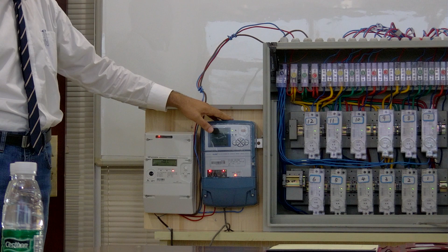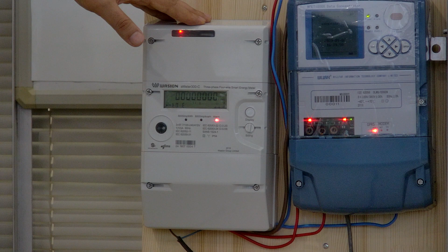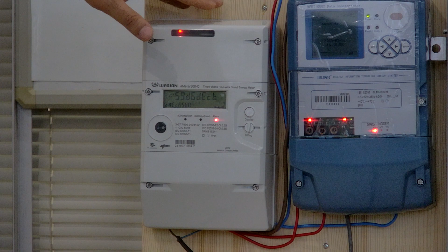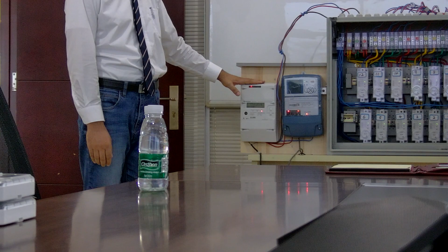The DCU is usually installed next to the distribution transformer at the beginning of the feeder, where we also usually have a CT or CT-PT meter installed at the primary or secondary side of the distribution transformer. It's used for measuring the energy delivered by the transformer as well as monitoring electrical parameters like voltage, current, THD and others. So this is the transformer meter, usually installed at the beginning of the feeder.